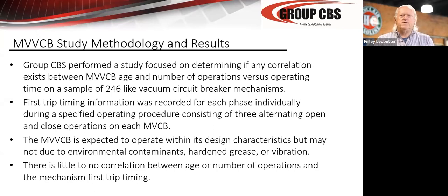The vacuum interrupter itself may not last 40 or 50 years. If the breaker is a modern breaker, the vacuum interrupters will not live 40 or 50 years. If the breaker was built by certain manufacturers in the 80s, the material sciences and the way they were designed, they have a little longer shelf life than they have today. But the majority of the modern vacuum interrupters are made in Asia, in China in particular, and we have a lot of infant failures with them. We have very high leak rates, and you're not going to get 40 or 50 years out of a modern breaker unless it's made by certain manufacturers. There are some manufacturers that have very low leak rates, and their vacuum interrupters will survive for a longer period of time.